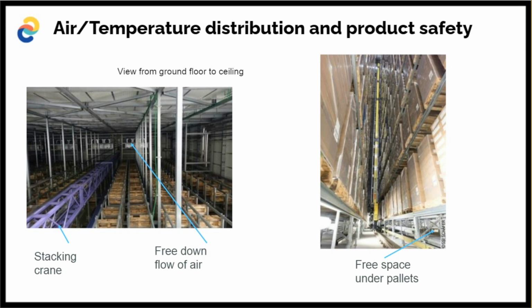We're now at one end and we are looking up, and we see here the fans of the coolers blowing down. That has to be completely free, and the air must flow nicely and not be disturbed by the stacking cranes. And we need some free space under the pallets, like you see here, on the right one. So during the construction of the high bay, you need to take that into account, that there is a free flow of air.